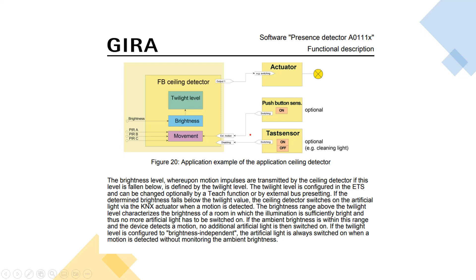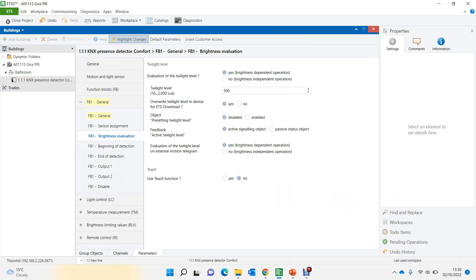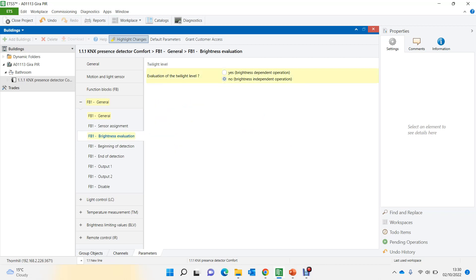The ceiling detector first checks brightness — whether there is enough light in the room. If there is enough light, movement detection is effectively disabled and no commands are sent. If there isn't enough light, it will send commands. When I disable the brightness option, the brightness function disappears and it becomes a pure movement detector — every time there is movement it will act on it. It no longer looks at the light level at all: movement turns the light on, end of movement turns it off.